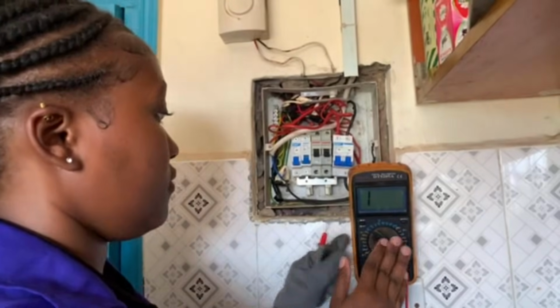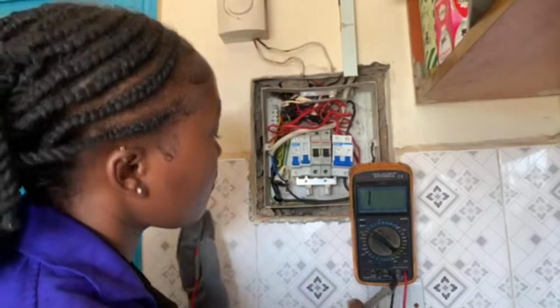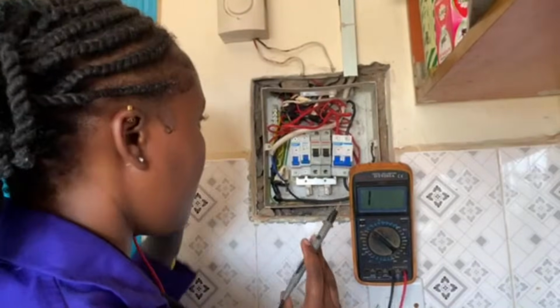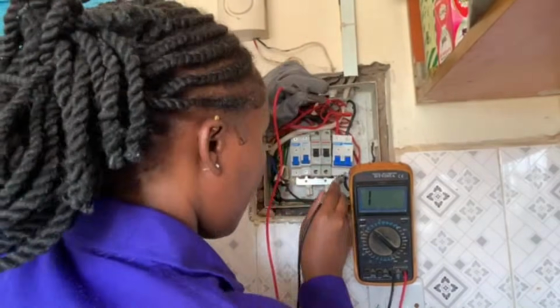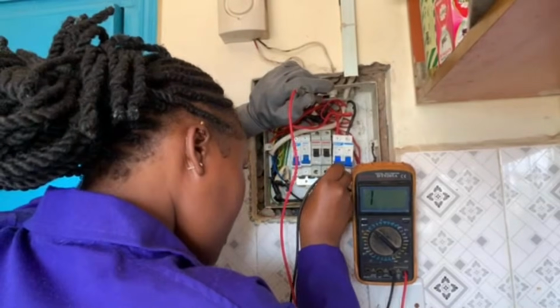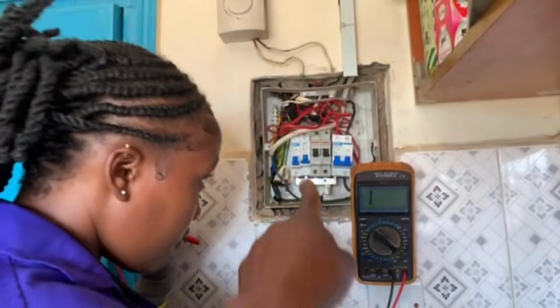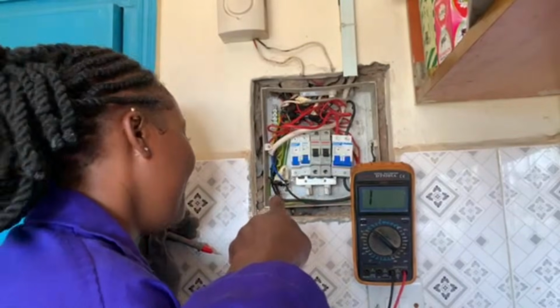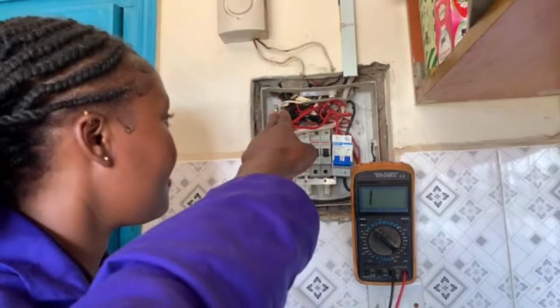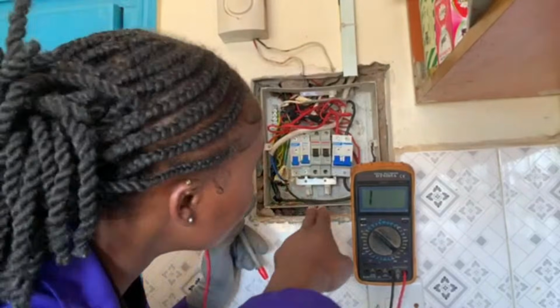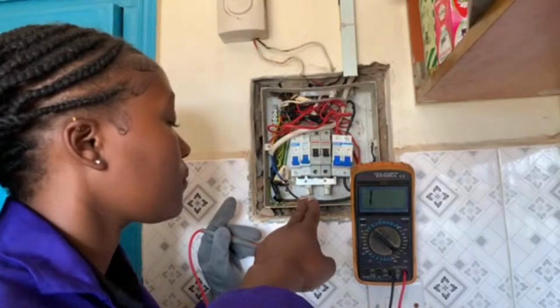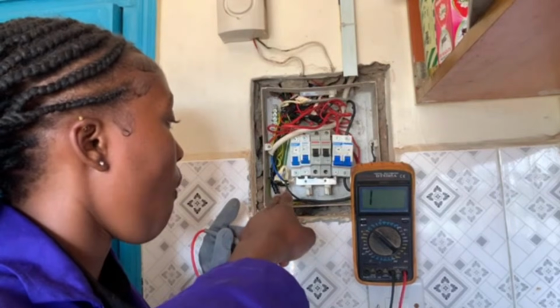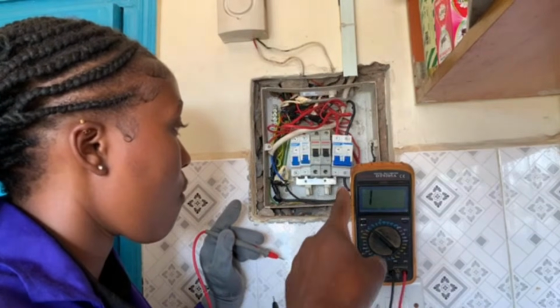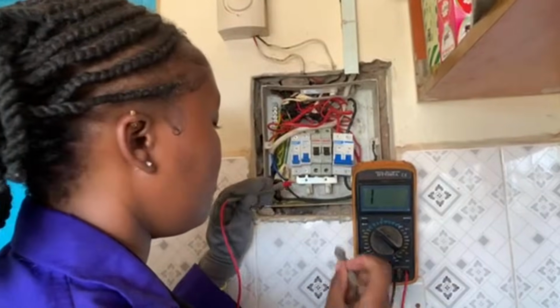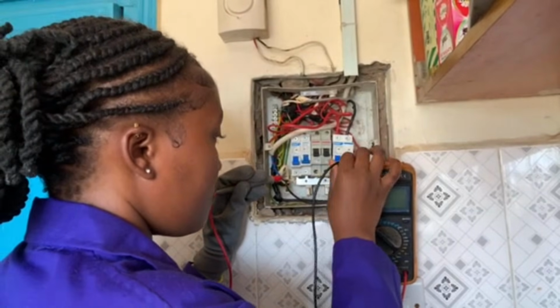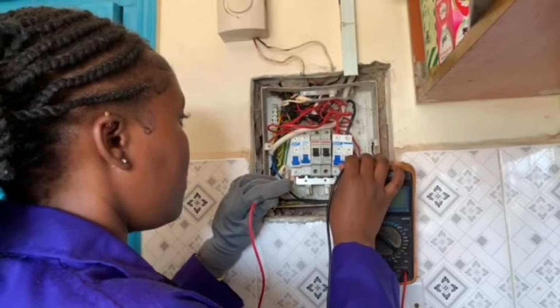Good job. We then place the probe on the screw, on the output of the neutral, okay, because it is sealed. This is a bad connection - if we had a bar exposed, like on the earthing, we would have done the procedure you're about to do. But since it's insulated, do that with the line on the output and then on the individual MCBs.